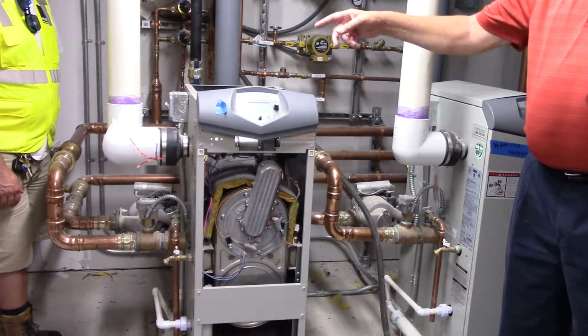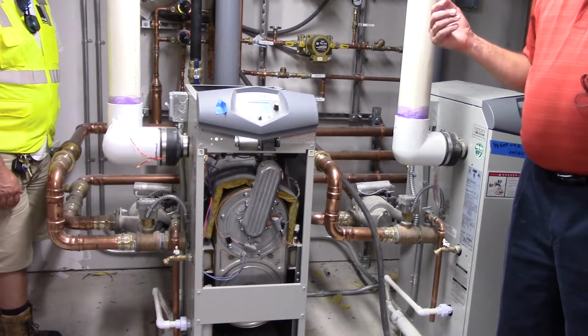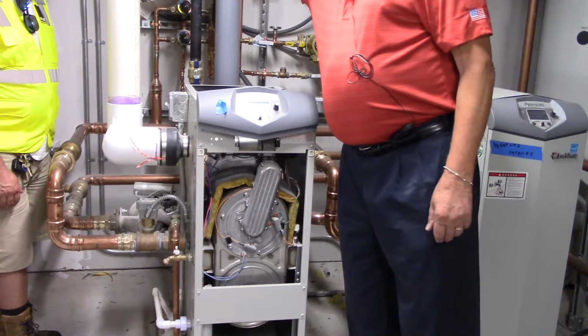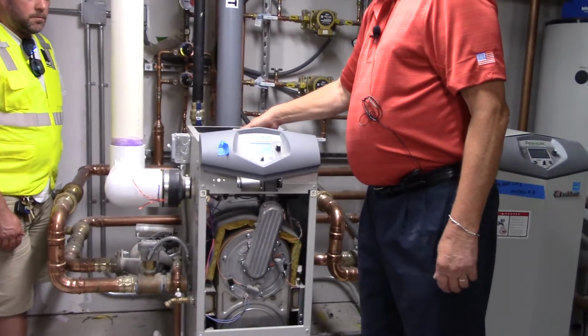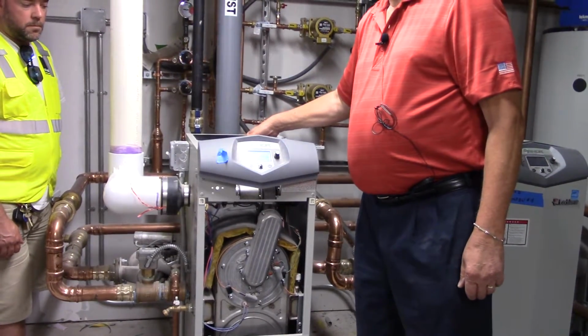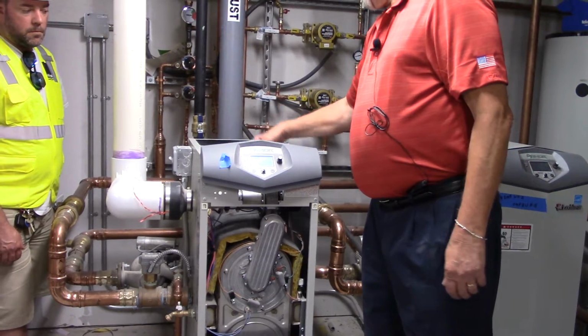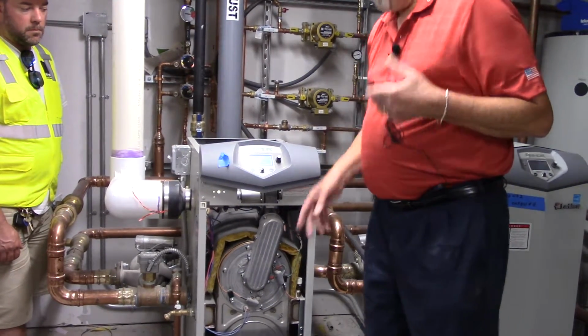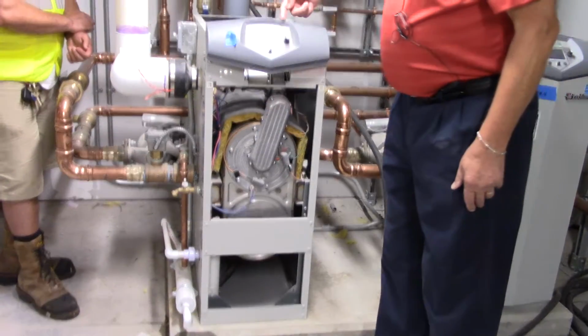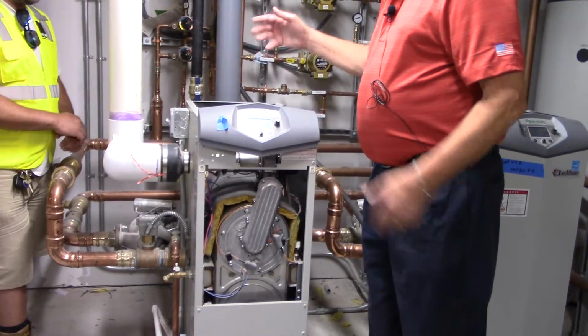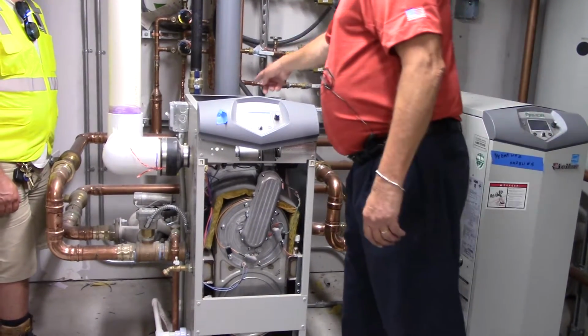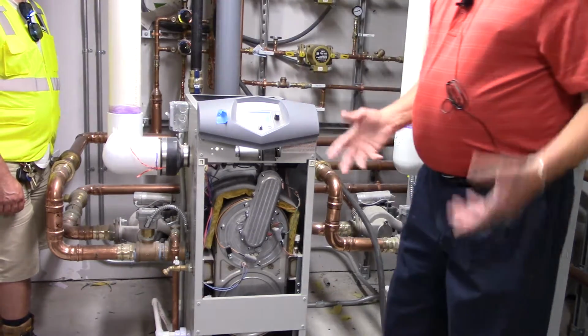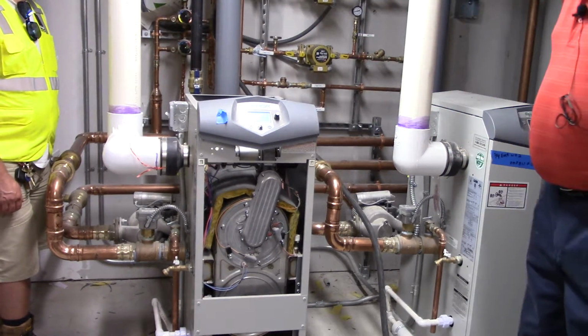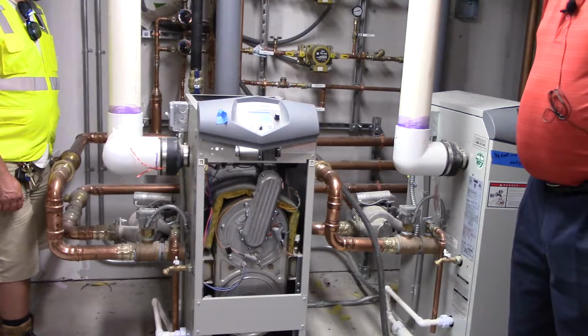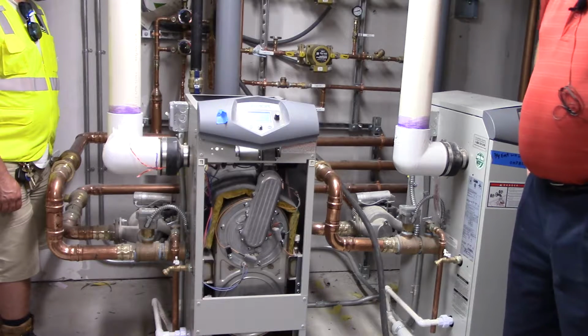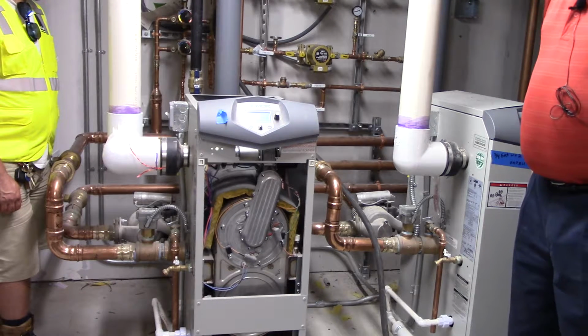If the water gets this far, your fan's going to suck it in anyway. Because your fan is pulling in, this is like an open-ended system. Your fan's pulling air in here, right into here through a venturi. You've got a gas valve that's a solenoid valve. That snaps open. The fan pulls the air and gas through, down the arm into the burner. The burner runs the length of the heat exchanger. And like I said, then it propels it out through the exhaust and out of your building. So it is an open-ended system. So I don't anticipate you'll have an issue with that. I haven't had that be a problem. Any other questions?